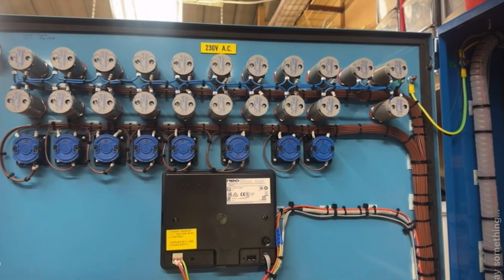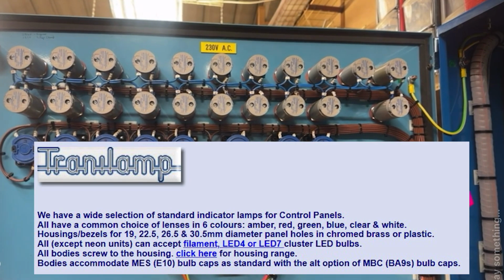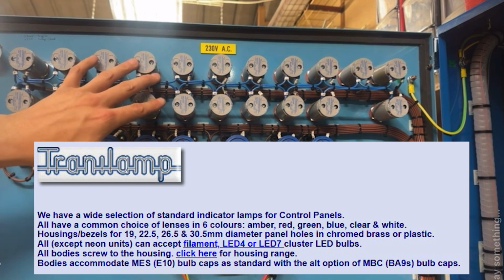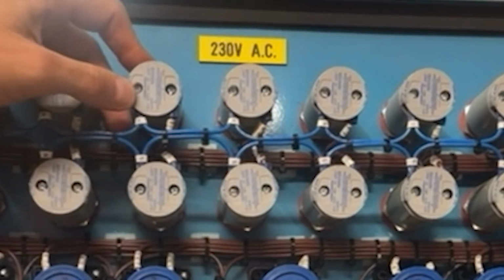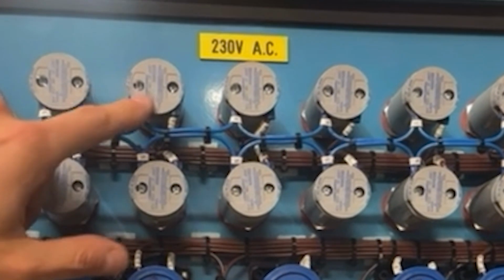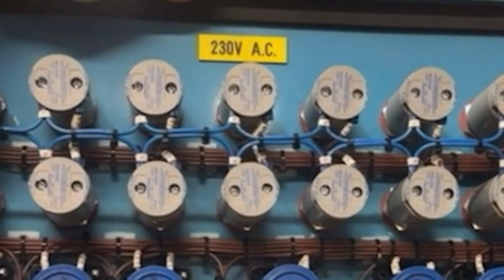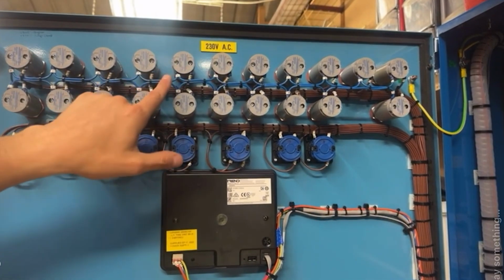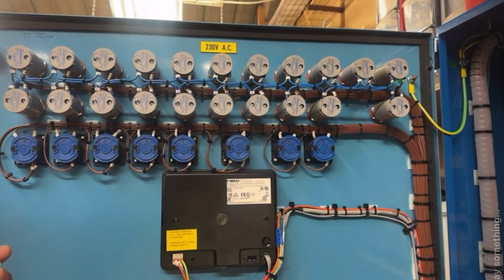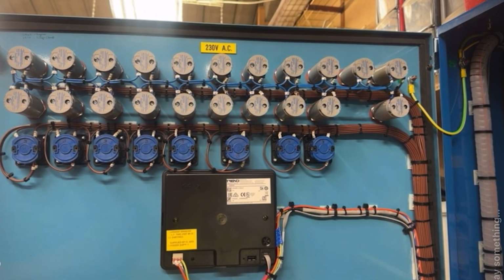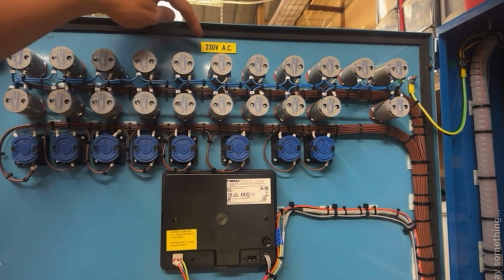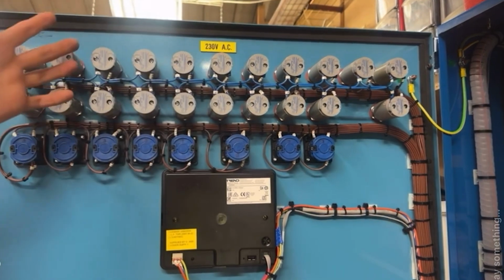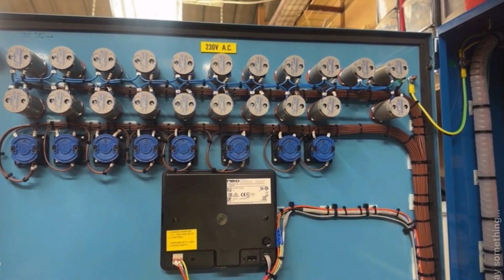They're called tranny lamps. The reason they're called tranny lamps is because they take 240 volts, but then transform it on the transforming side into a voltage that lights the lamp on the front at a much lower voltage. I think in this case these will be 24s. They are 6 volts, so they've got to get a load of 6 volt lamps for it. It's all marked 230 volt AC, but the actual lamps at the front are 6 volts, so be aware, that can catch you out.